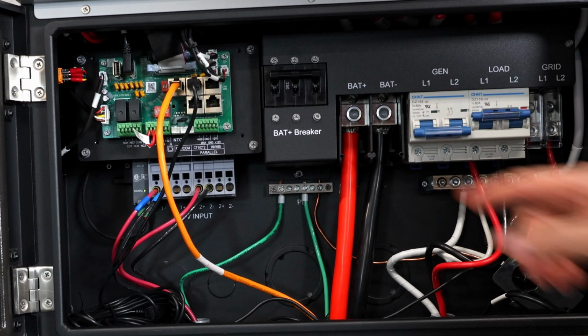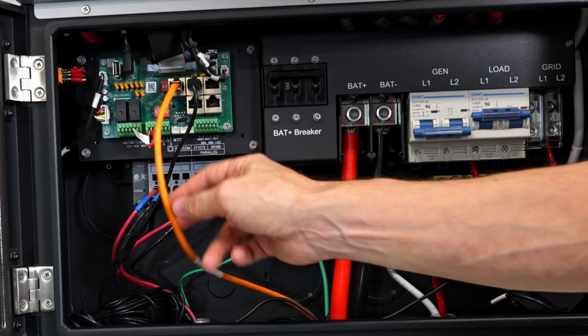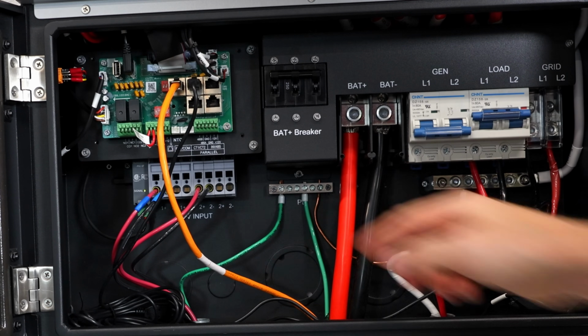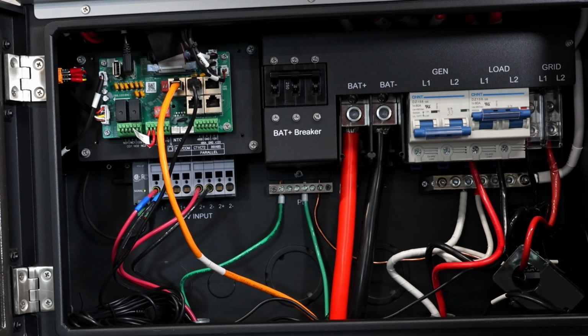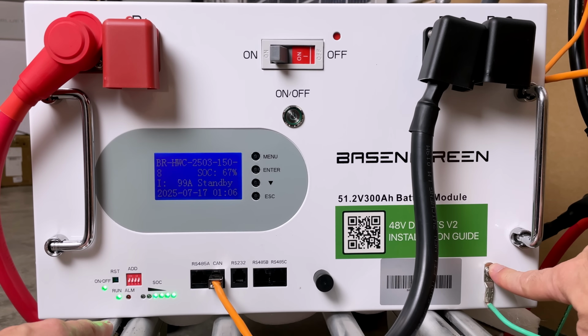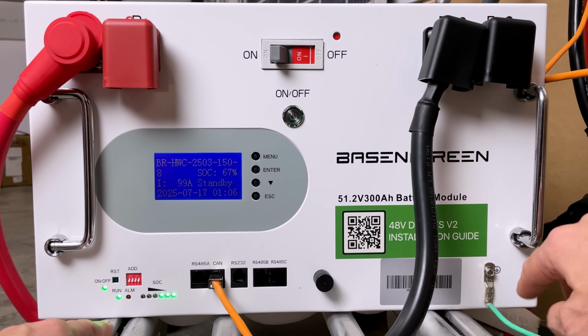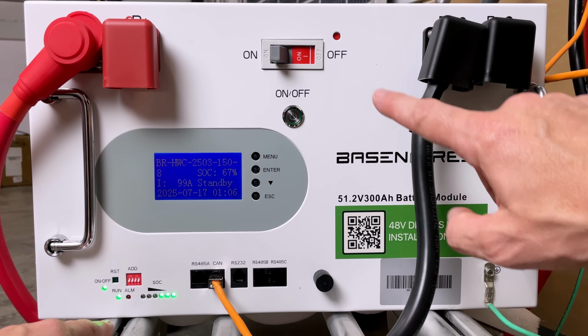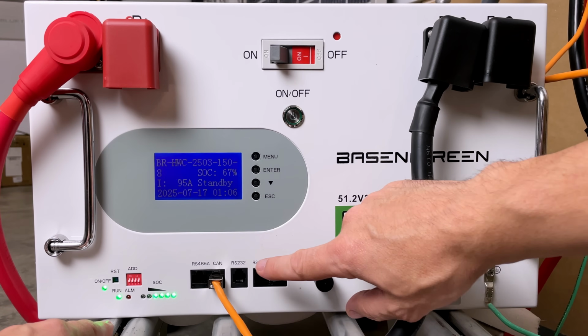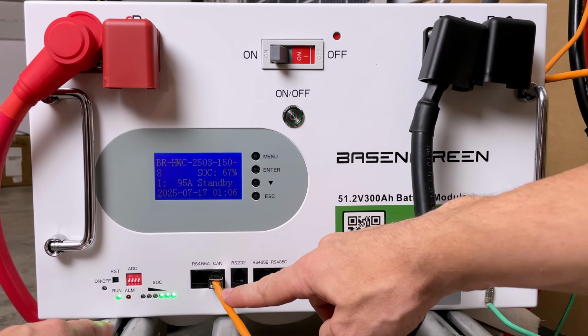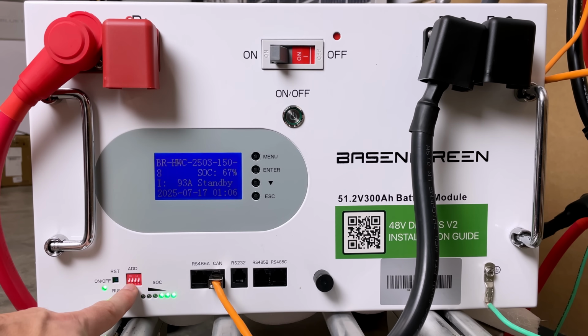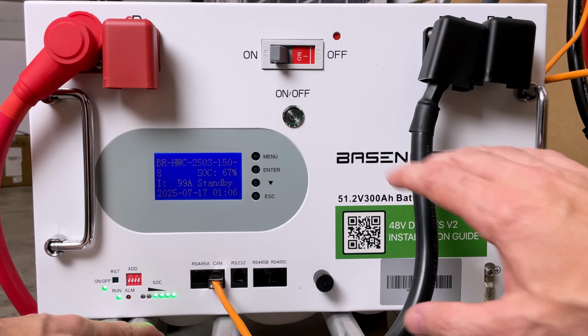I've connected this battery using 2-aught DC cables. I'm using a regular Ethernet cable for communications to the battery port, and I'm connecting the ground wire to our ground bus here to bond the case to the rest of the system. At the battery end, my 2-aught cables are just coming into the plus and minus, and the communication cable I have connected to the CAN port. For the BMS, I have the dip switches all in the off position for battery 0, since this is the one that's communicating.